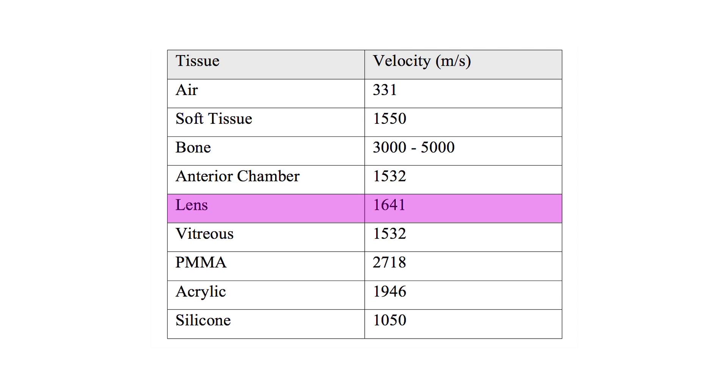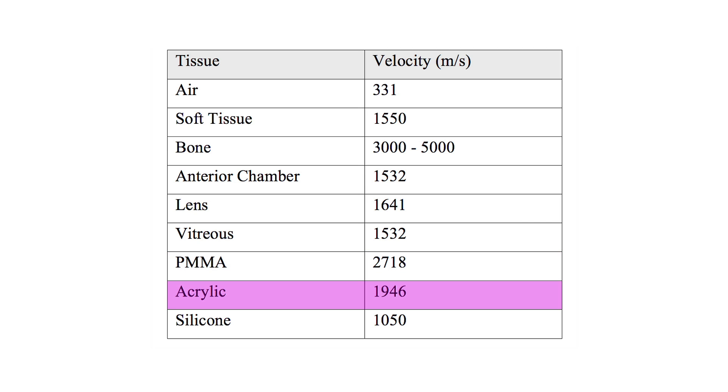In the pseudophacic eye, the speed varies according to the material properties of the intraocular lens. The velocity through an IOL made of PMMA is 2,718 meters per second. Through an acrylic IOL, 1,946 meters per second. And through a silicone IOL, 1,050 meters per second.